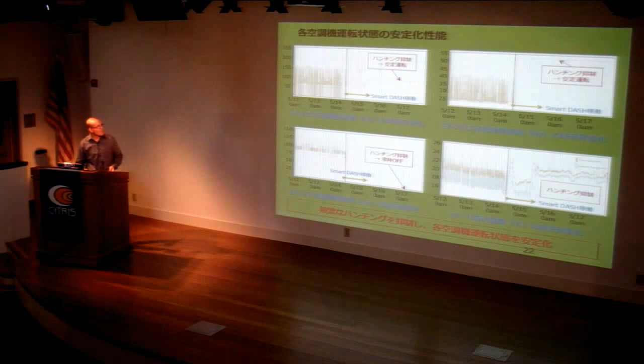This allows us to raise the temperature, and yet the peak temperatures don't go any higher than before. So we're able to get savings not only from stopping all of this thrashing—there's a ton of energy wasted by all these starts, stops, and cycles—but also by raising the average temperature of the data center considerably, increasing the efficiency of the equipment and reducing the losses to the rest of the facility.